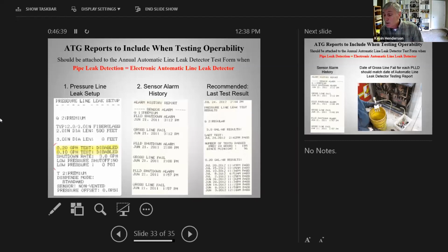You need to make sure, part of the annual functionality test, of course, is making sure that the setup is correct. Having 500 feet of fiberglass pipe is unusual at a typical gas station. Sure, it's possible, but you need to make sure that that is correct. The Veeder manuals will tell you that pipe has to be within like 10% of the actual length for it to be accurate. So you better have a pretty good idea of how far the distance is between the submersible and the location.